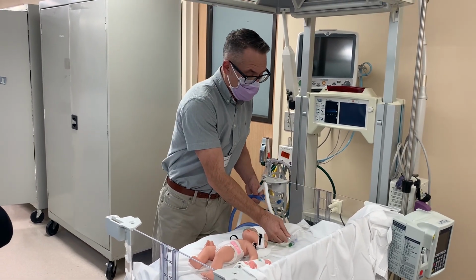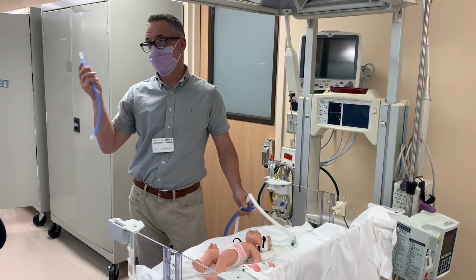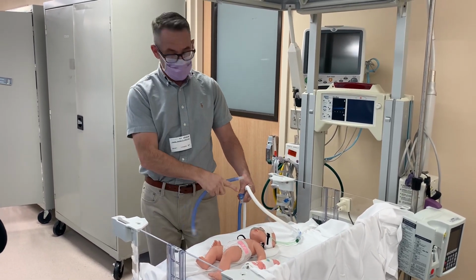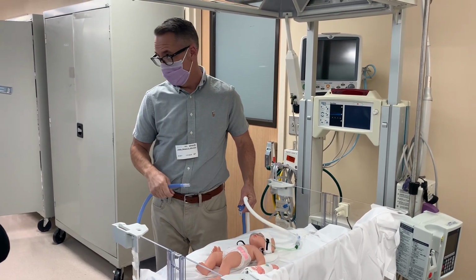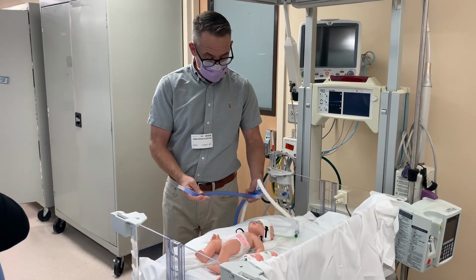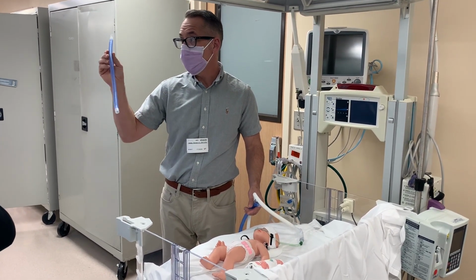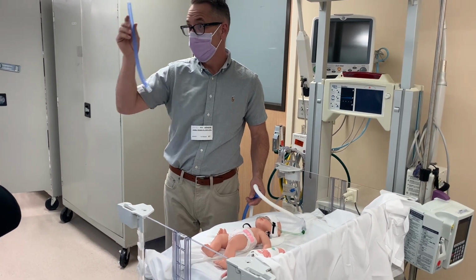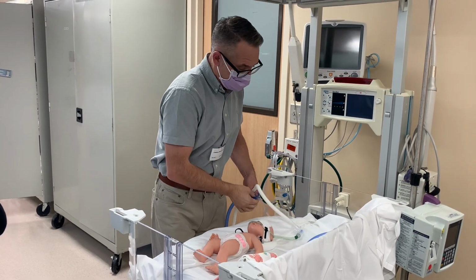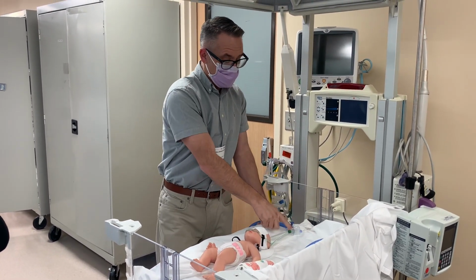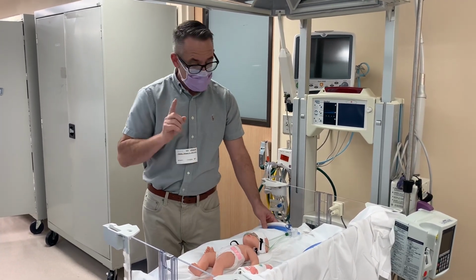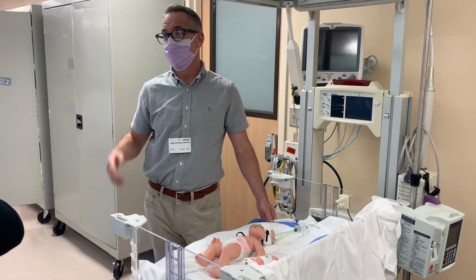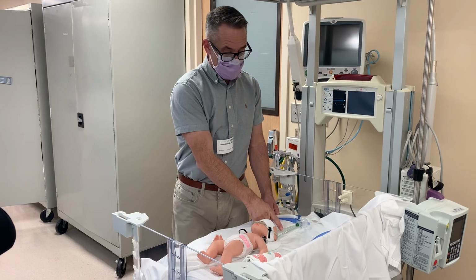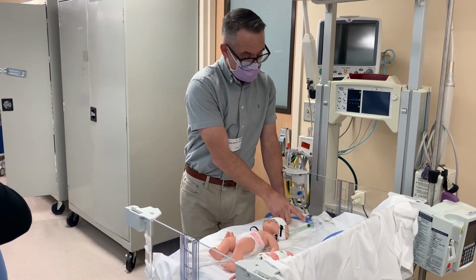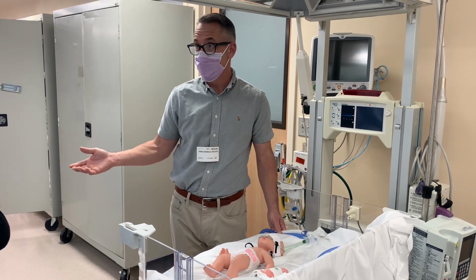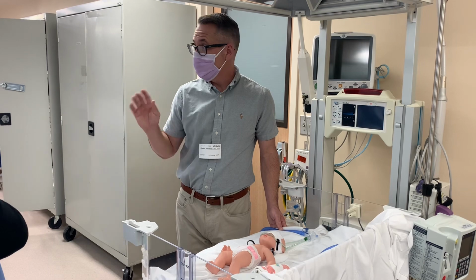Number one, all of your RT265s come with this extension unit. We've been trained over the years that you had to use an extension unit to keep the temperature probe out of the incubator. You don't have to do that anymore. I'll explain that in a minute. But what you're doing when you're taking out the extension unit is you're taking out 10, 12 inches. So you're taking out 6 degrees of potential droppage and all the water that accumulates into that. So now we've cut that down. So 40 degrees goes here rather than way back here, and then all this stuff is dropping. The tricky part is because you guys use the RAM cannula, the cannulas by their very nature do increase rainout because they have high resistance tubing where air is being pushed into it. And then this is a very long piece rather than a true CPAP idea. But this is what you guys use, so we're going to make this work.